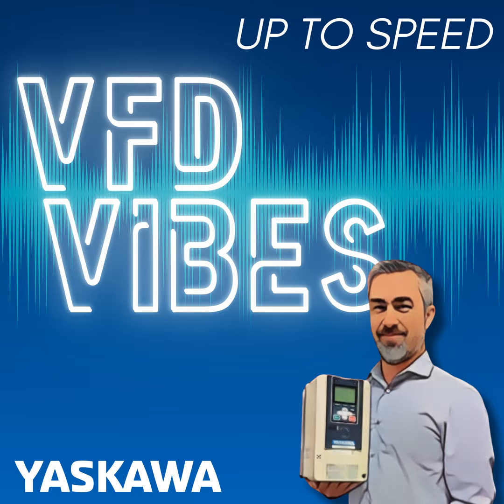If you're talking outdoors, type 3R is usually sufficient. Type 3R is going to include things like rain hoods, filtered ventilation, maybe a space heater as an option. And the space heater is not necessarily designed to keep the drive warm and toasty on a cold night.